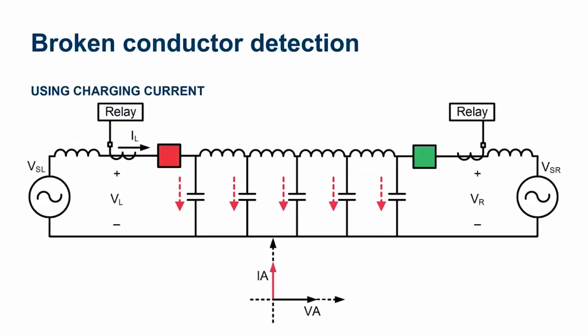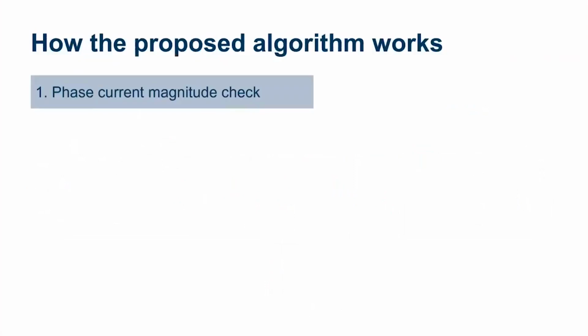What this really does is take a look at the relationship between the current and the voltage. How this algorithm is going to work is it's first going to take a look at the phase current magnitude. This is going to be satisfied when the magnitude of the phase current is less than the charging current for that phase. For those of you who are familiar with the 411L, we've got charging current compensation that is available for our 87L element. So we can calculate the charging current that the line is seeing; the relay can calculate that. During a broken conductor, the charging current that's going to be measured is going to be up to the break point of the line, and so that should be less than the total charging current of the line. So first we check: has our phase current magnitude decreased, has our charging current decreased.